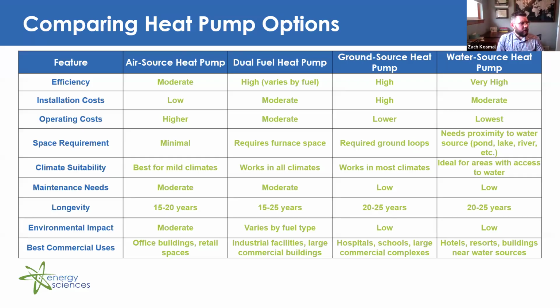Moving on to climate suitability. So an air source heat pump is best for mild climates. Dual fuel heat pumps work in all climates, but if you're in a warmer climate, you may not need that dual fuel furnace backup. I'm imagining that most of us are in Michigan, where that dual fuel heat pump definitely comes into play during that winter period. So keep that in mind. Ground source heat pumps, they work in most climates. Your biggest issue with ground source heat pumps is that ground soil that you're dealing with. And I'll go into more detail about that in a little bit.